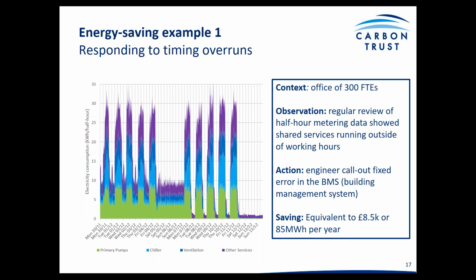This is an example of a site that the Carbon Trust was monitoring - an office of approximately 300 employees. Following routine maintenance of the HVAC system, the controls of the main system did not operate as they were supposed to, with the cooling, ventilation and associated systems being left on 24/7.